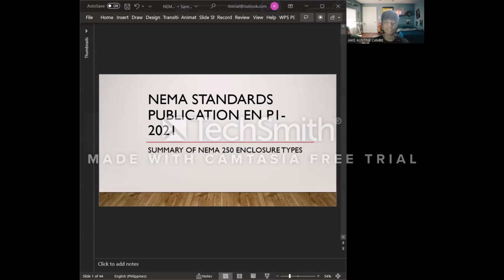So before I start, let me discuss what an enclosure is. An electrical enclosure is a cabinet or a box that protects electrical or electronic equipment and prevents electrical shock. Enclosures are usually made from rigid plastics or metals such as steel, stainless steel, or even aluminum. Enclosures are rated to designate protection against hazardous and non-hazardous and even other specific environmental conditions.